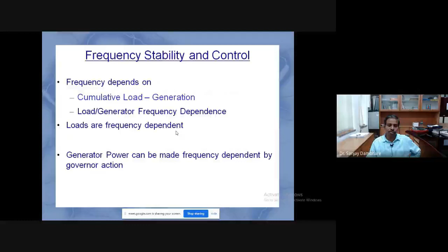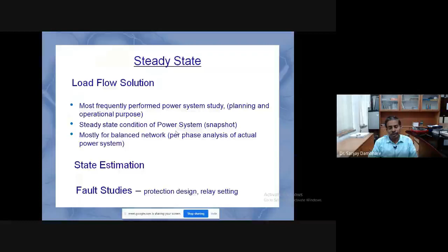Okay, so this we have already talked of, and when it comes to the steady state, we have this load flow solution, which is important for the power system protection engineer also. And the fault studies are more important for the power system protection engineer also, because the protection system design, the protection system relay settings and circuit breaker selections and all that will depend upon the fault current.